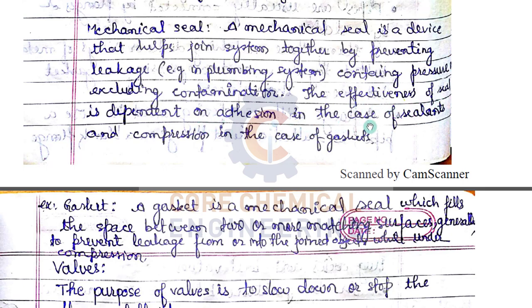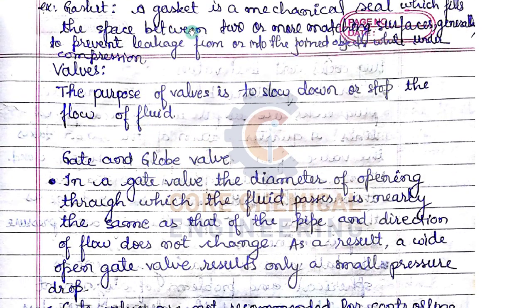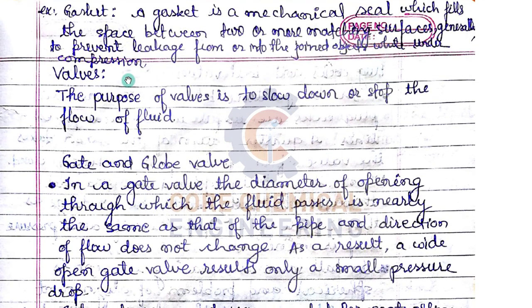A stuffing box is an assembly used to house a gland seal, preventing leakage of fluid such as water or steam between sliding and turning parts. A mechanical seal joins system components together by preventing leakage, containing pressure, and excluding contamination. The effectiveness of a seal depends on the adhesion of sealant or, in the case of gaskets, the compression applied. A gasket is a mechanical seal that fills the space between two matching surfaces to prevent leakage while under compression.